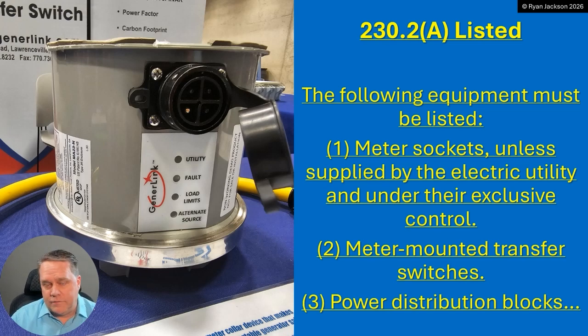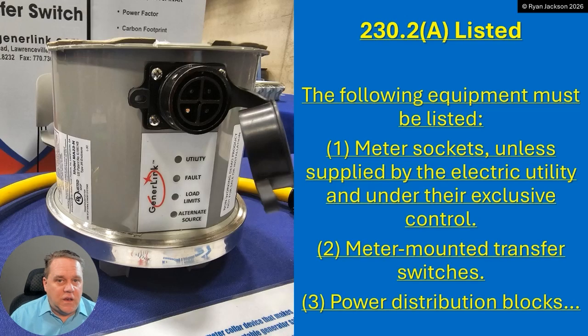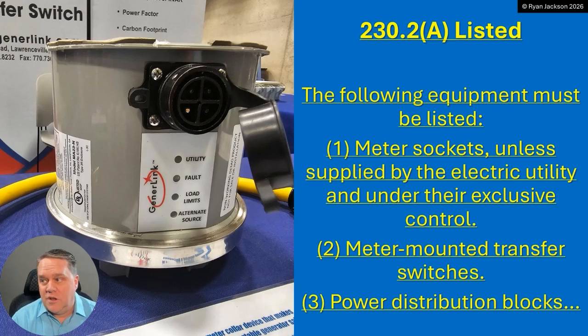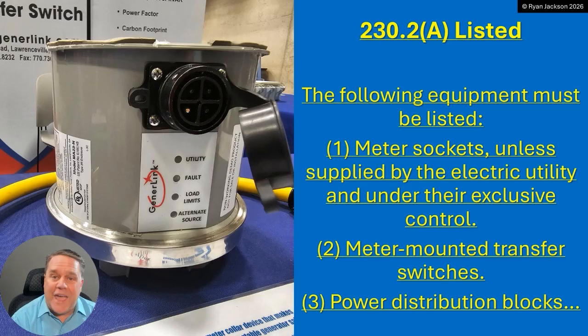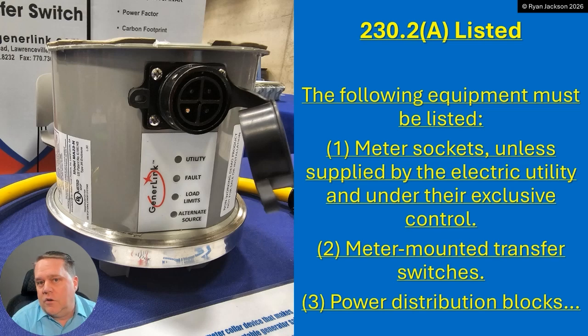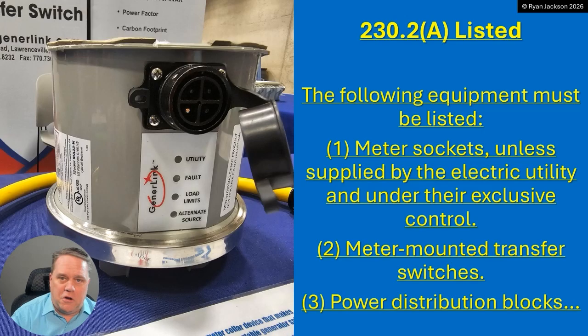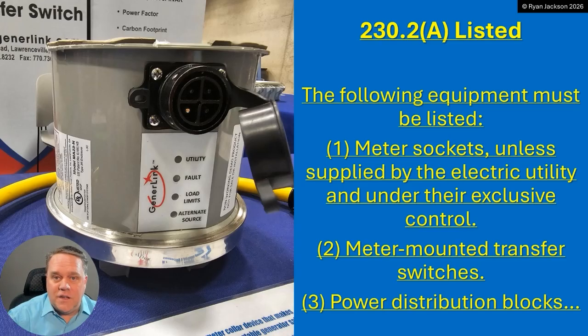Contrary to popular belief, not everything in the NEC has to be listed. In fact, a lot of stuff doesn't — motors, transformers, panel boards, switchboards, switchgear. In the 2026 code, if you go to Annex A, they actually broke it up into two parts: product standards for equipment that's required to be listed and product standards for equipment that are not required to be listed. So if you ever get in a fight with somebody that says everything has to be listed, show them Annex A where it specifically says here's stuff that doesn't need to be listed.